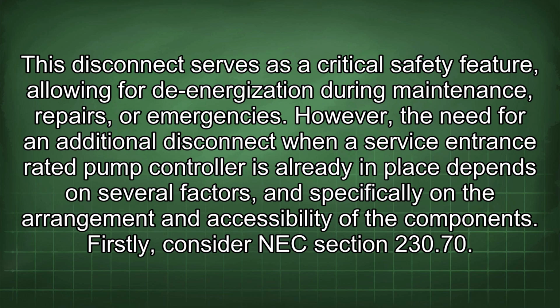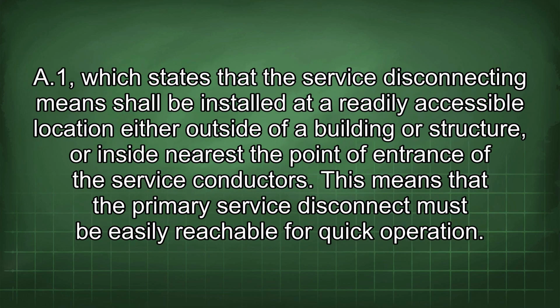Firstly, consider NEC section 230.70(A)(1), which states that the service disconnecting means shall be installed at a readily accessible location either outside of a building or structure or inside nearest the point of entrance of the service conductors. This means that the primary service disconnect must be easily reachable for quick operation.